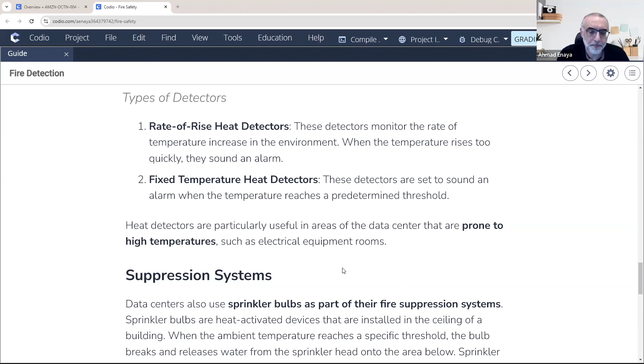So once we detect the fire, we need to suppress the fire. Detecting is important because we want people to leave the building. It is important to detect the fire as soon as possible to give people a chance to leave, and to give the fire department a chance to be alarmed and send the brigade. But there should also be a suppression system. If you remember, in the data center in France, they did not have a suppression system. There was no system to suppress the fire. They had only detectors. They depended on the fire department to send teams to suppress the fire. They didn't have their own system, while in proper cases, there should be a system for fire suppression. And this is the sprinklers. We will talk about sprinklers more in the coming slides.